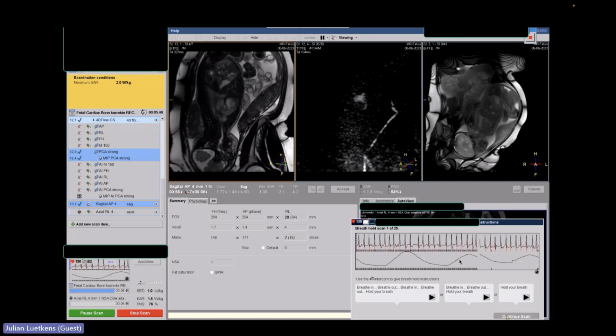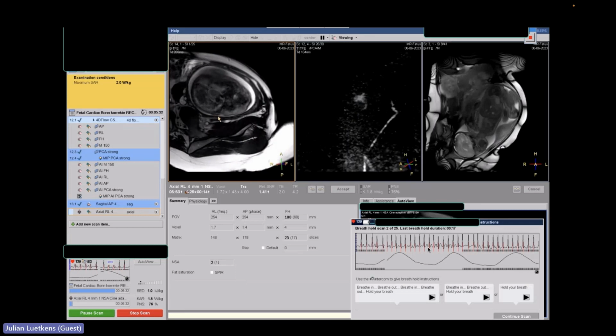Now you can see we already have this breath holding tab here, but the scanner is scanning right now due to the dashed lines. So we do it with 2 signal averages, but don't give the breathing command. So we just press continue scan without doing a breathing command, and we do slice by slice. You can also see that the SNR of the mother, of course, increases due to the 2 signal averages.